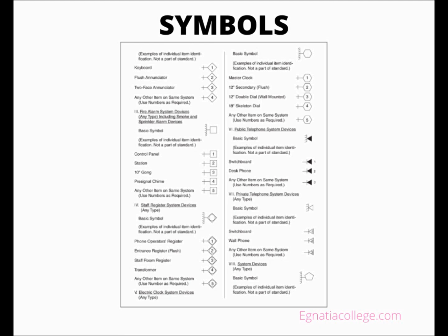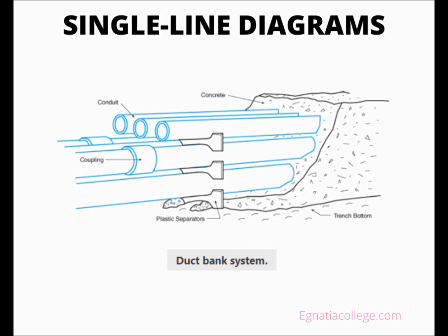Single-line diagrams. The electrical service single-line diagram on the school edition is shown on drawing E2, single-line diagram E17. The electric power is brought into the school by way of the service entrance section, SES. The note "coordinate with the local utility requirements prior to rough-in" indicates that the electrical contractor is to furnish and install the 3 4-inch conduits, and that the utility company wants to inspect the conduit installation prior to backfilling the trench where the conduits are installed. However, this should be verified at a pre-construction meeting with the utility company.